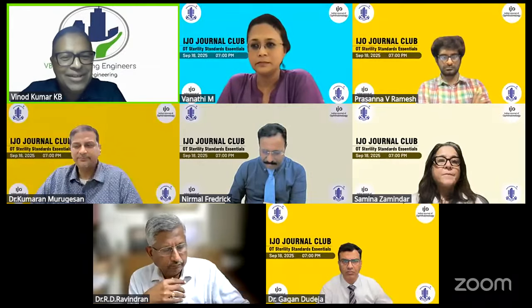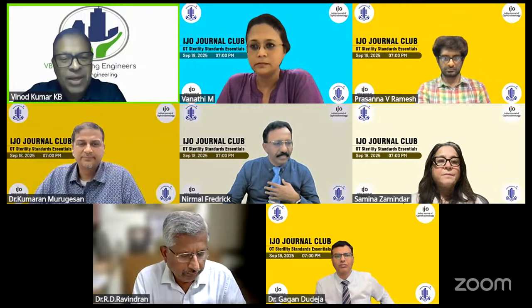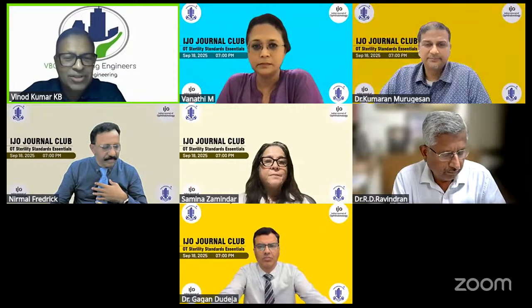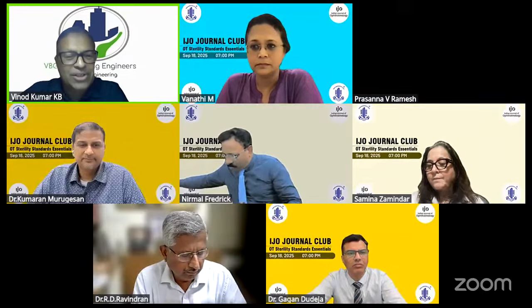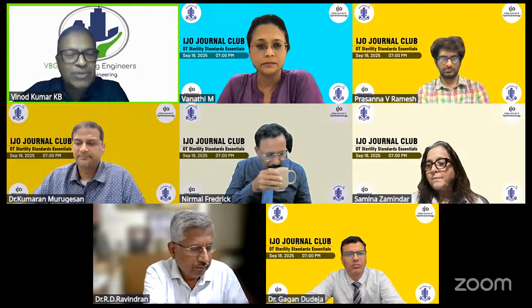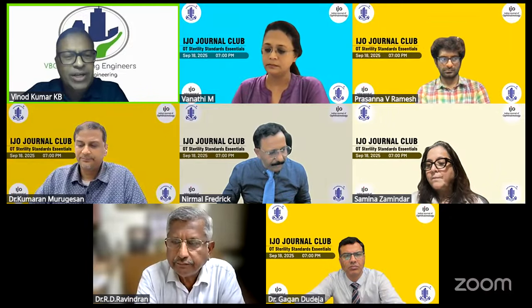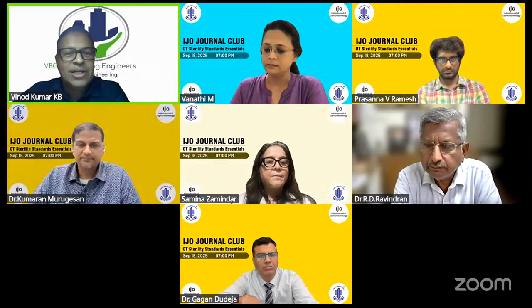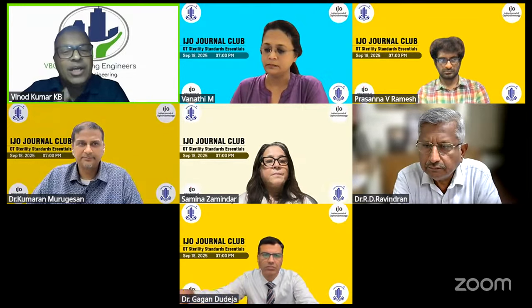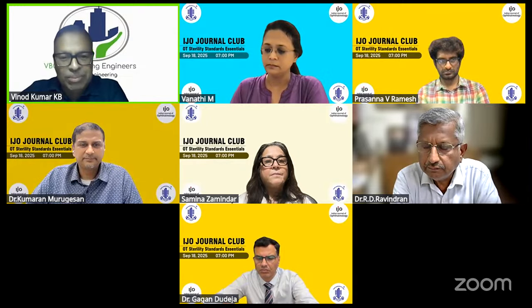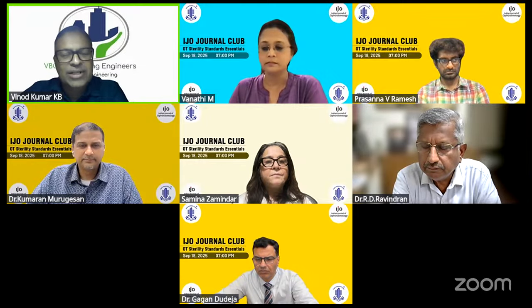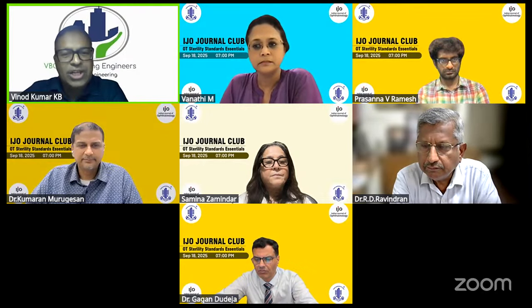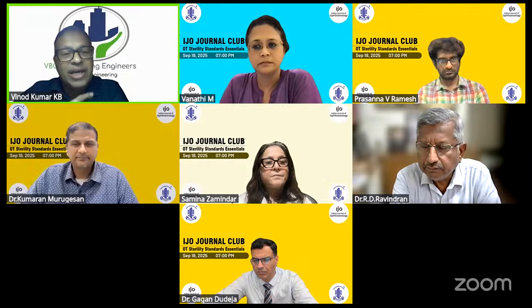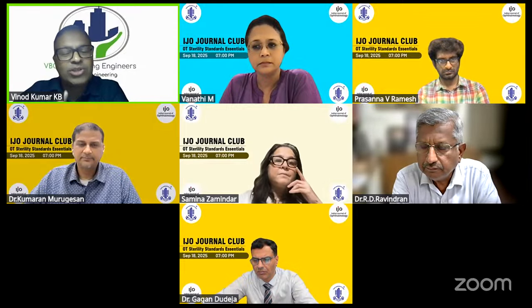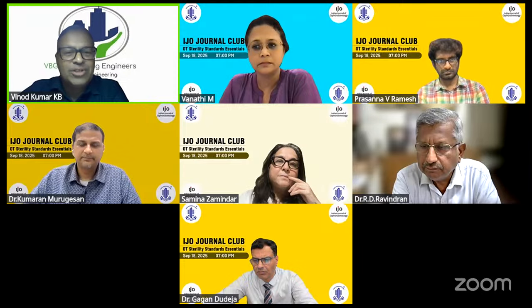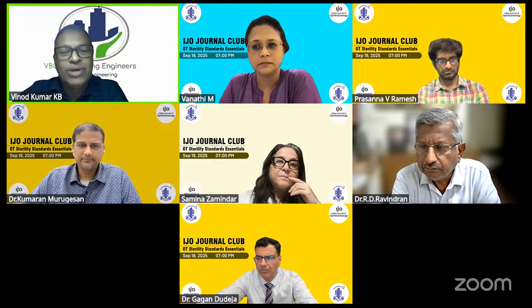Thank you, Dr. Kumaran, and thanks, Dr. Nirmal, for the good presentation. Coming to the air, whenever I talk about it, I talk about 2 points. One is prevention is better than cure, and next is air with care. So that talks about the air and the environment inside the theater. When we look at the number of people inside the theater, generally the standards talk about 5 to 7 or 5 to 8, but invariably during any surgical operation, we have more people. So though it's not mandated that CO2 or oxygen level is to be measured, the air change per hour becomes important, which talks about dilution, which talks about contamination control. So that takes care of this carbon dioxide removal as well.